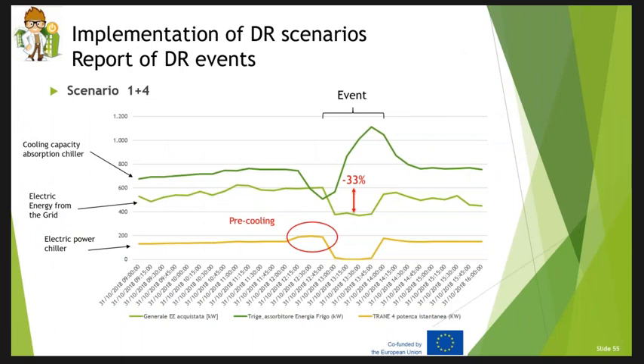This is also the same event that we were able to run in October. Also in this case, you can see the electrical power of the chiller is the yellow line in the graph. The electric energy from the grid, so the total consumption of the hospital, is the light green. And when we ran the event, in this case around 1 to 2 p.m., we recorded a decrease of energy consumption by 33%.